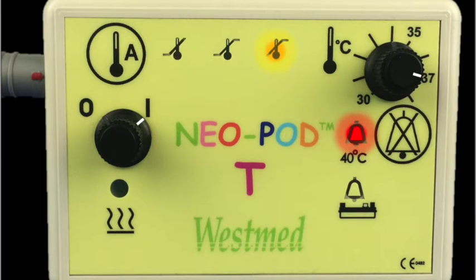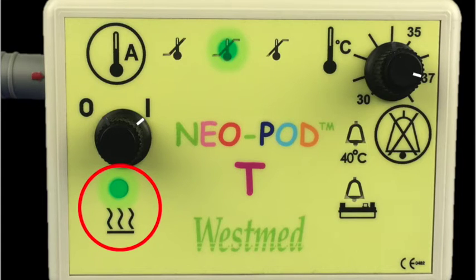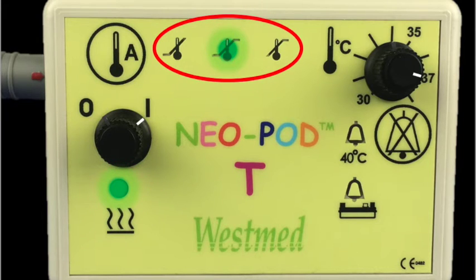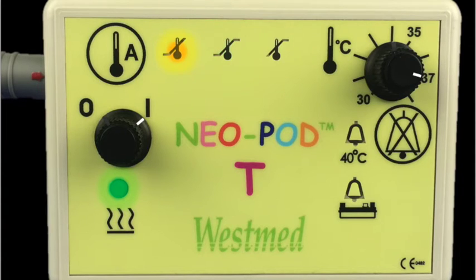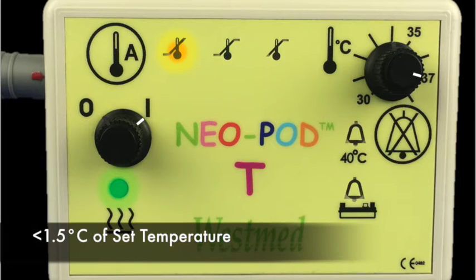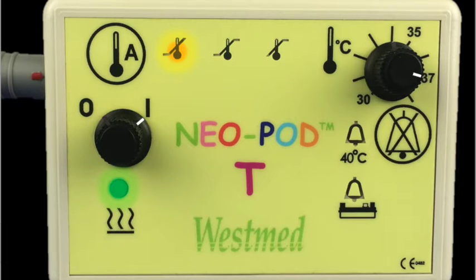There are several LED lights on the face of the controller. Beneath the on-off switch is illuminated green whenever power is being applied to the heater in the LavaBed cartridge. There are 3 LED lights in the center of the controller. The LED on the left is illuminated yellow whenever the monitored temperature of the LavaBed or airway is 1.5 degrees centigrade or more below the temperature set on the temperature control.